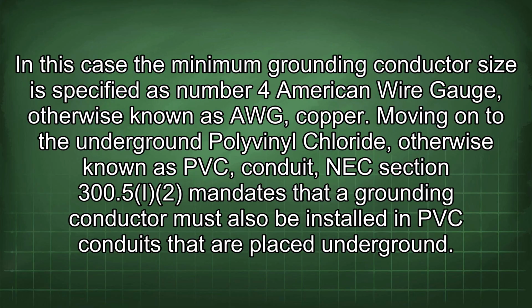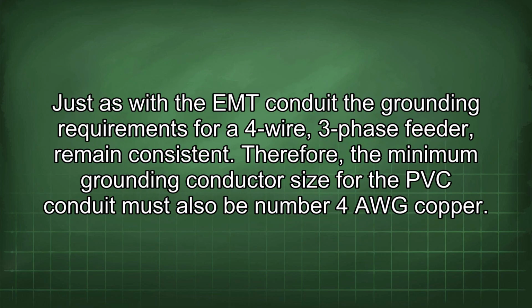copper. Moving on to the underground polyvinyl chloride, otherwise known as PVC conduit, NEC Section 300.5 mandates that a grounding conductor must also be installed in PVC conduits that are placed underground. Just as with the EMT conduit, the grounding requirements for a 4-wire, 3-phase feeder remain consistent. Therefore, the minimum grounding conductor size for the PVC conduit must also be number 4 AWG copper.